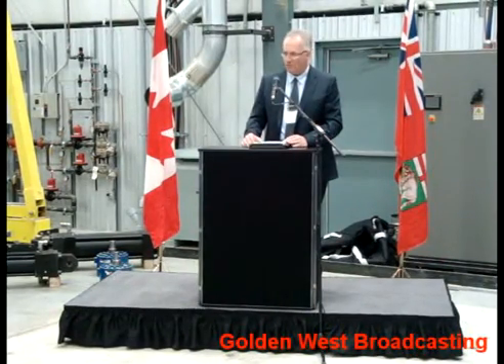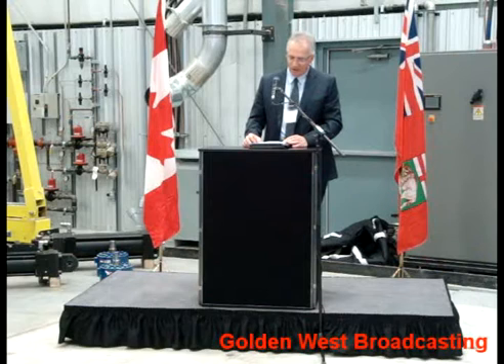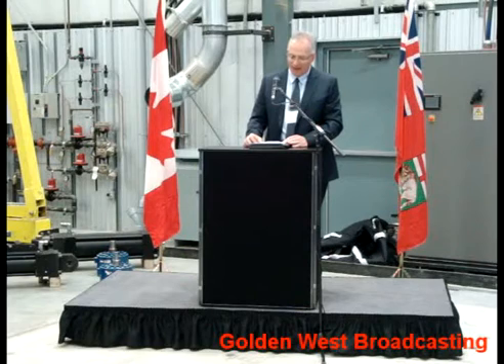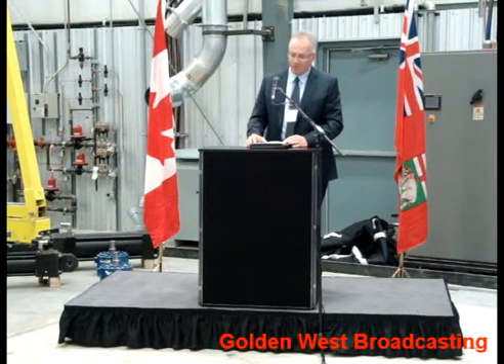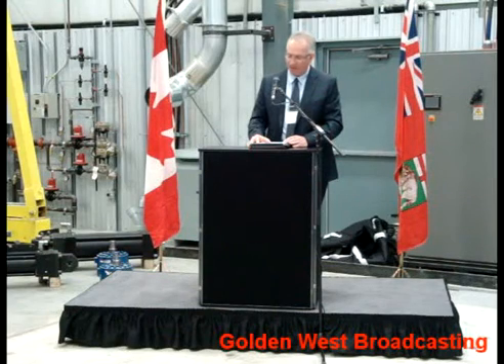So now I'm going to go into the course part. Internal combustion engines today run at about a 33% efficiency. This means that when you want to test something that's got 500 horsepower coming out of the back end of it, you need to worry about manipulating 1,500 horsepower worth of power, which is burnt in the diesel fuel going into it. So in order to do that, you've got to go ahead and handle the other 1,000 horsepower as well as the original 500 horsepower you wanted to test.